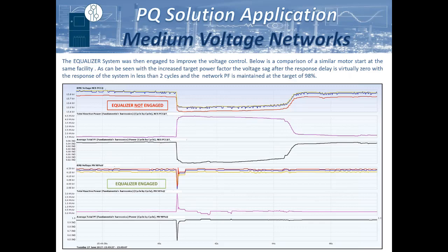One of the things that we've oftentimes seen is that after stabilizing the voltage on the network throughout, we have clients that see a 50 to 80% reduction in their VFD repair and replacement costs. The reason for that is that if a VFD is trying to maintain a constant speed or a constant torque, but the supply voltage it's being fed from on that circuit has other loads constantly coming in and out or inducing harmonics, the VFD has to have a response.